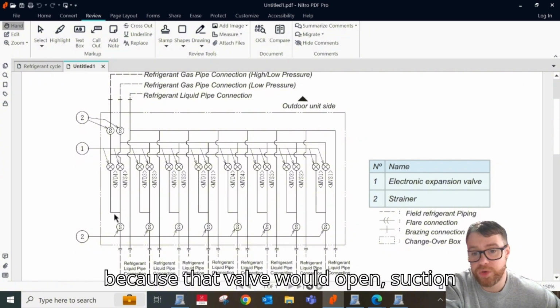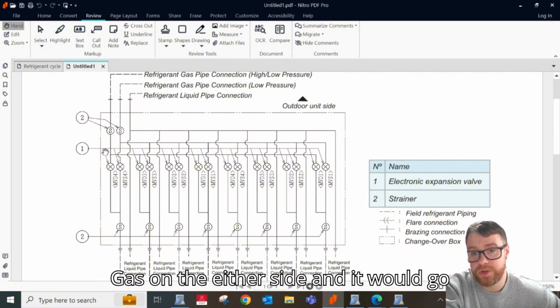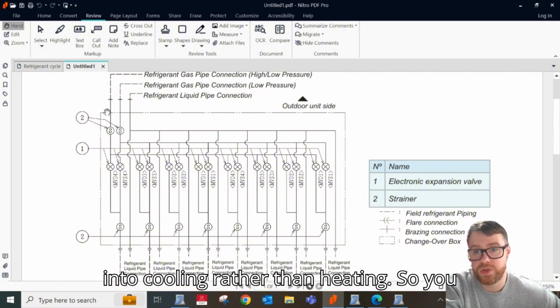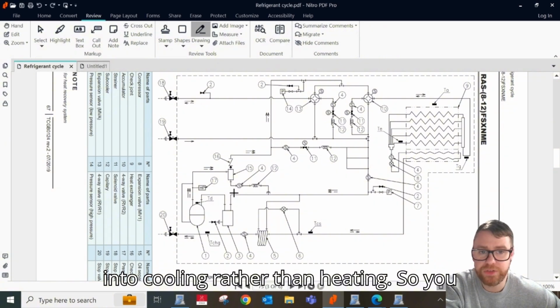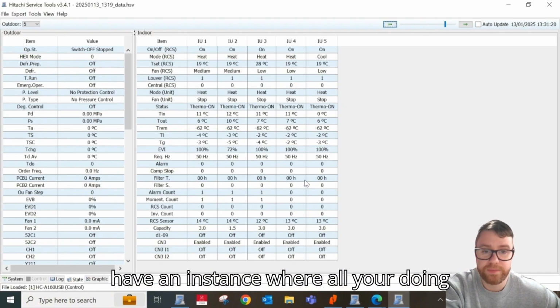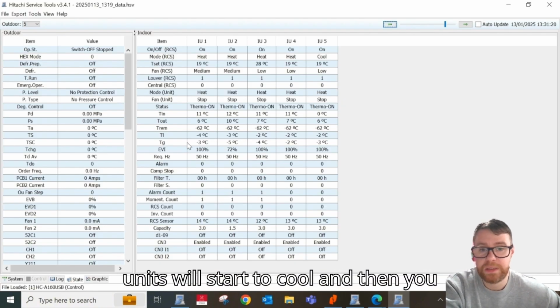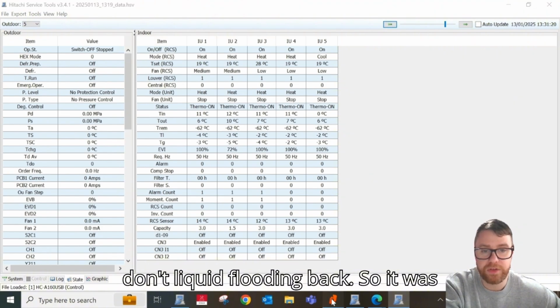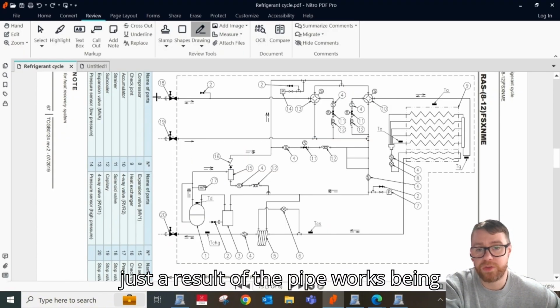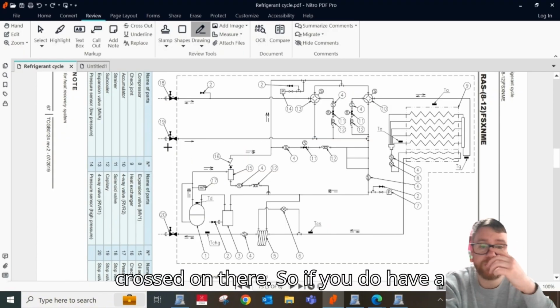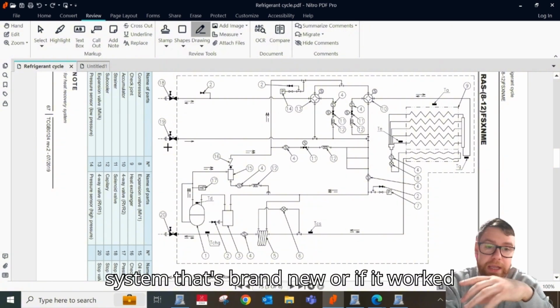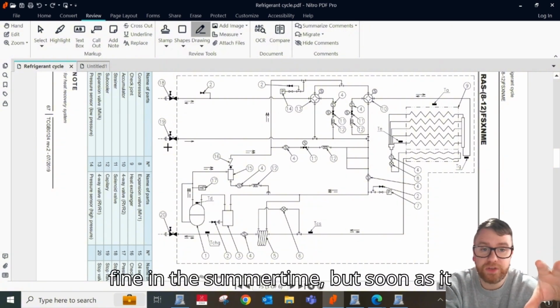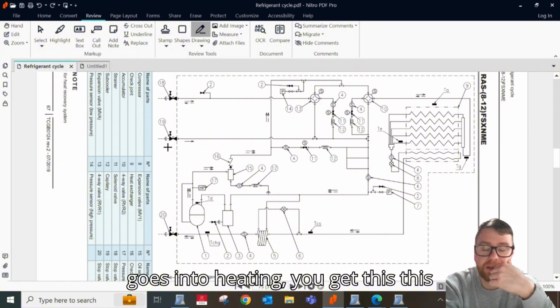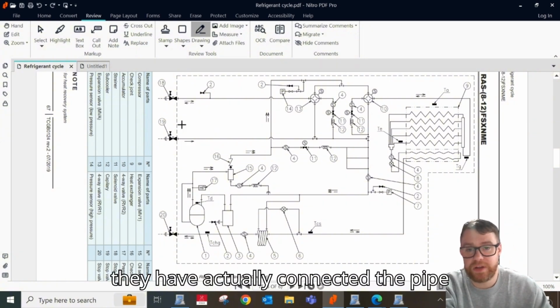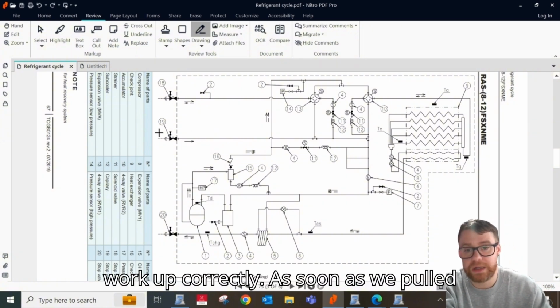And then the units were going to cooling because that valve would open, suction gas on the other side, and it would go into cooling rather than heating. So you would have an instance where all your indoor units would start to cool and then you'd have liquid flooding back. So it was just a result of the pipework being crossed on there. So if you do have a system that's brand new, or if it worked fine in the summertime, but as soon as any units go to heating, you're getting this problem, then just check that they've actually connected the pipework up correctly on the outdoor unit.